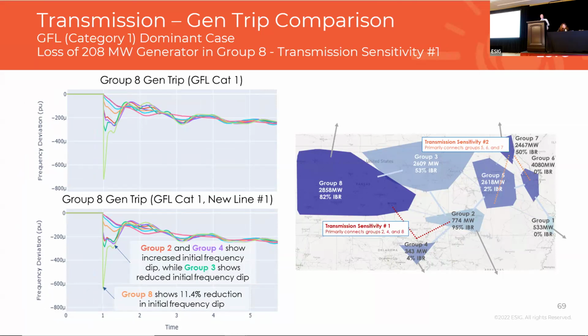Similarly, with a generation trip, zooming in on the transmission 1 sensitivity, when we compare, again looking at the grid following case—and frankly we started with the grid following case because the results show up a bit more—we can see the improvement here. Groups 2 and 4 show an increased initial frequency dip, while group 3 shows a reduced initial frequency dip.